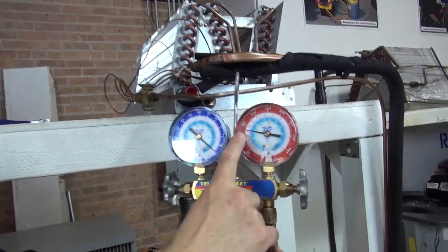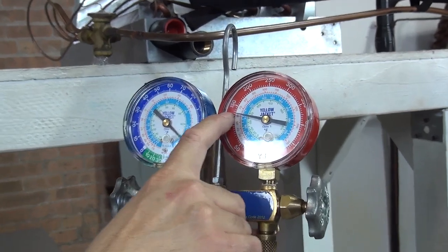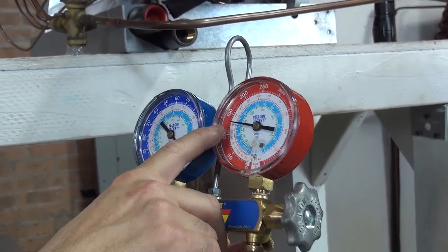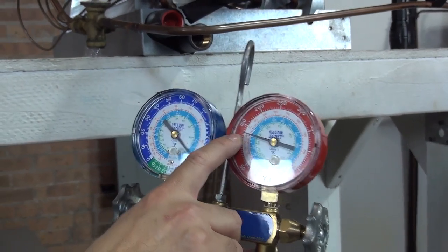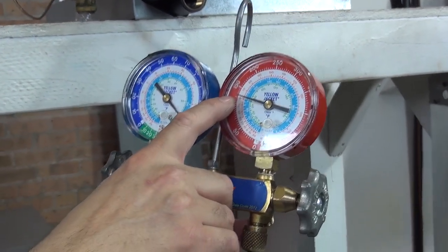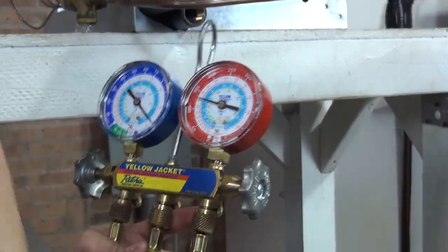Now the question is, okay, oh, by the way, get close. Look at what happened to pressure. Remember, we added all the way to 150, and my high side went down to, looks like about 135 or 130. So that definitely we had a leak. No more leak, it's gone. Okay? Now, since we found the leak, everything's cool.